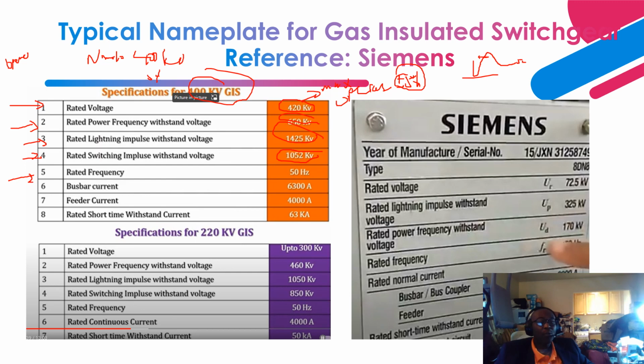Next is the rated frequency. Worldwide we either have 50 Hz or 60 Hz, right? Then the busbar current. For a GIS, we have a horizontal busbar, phase A, phase B, phase C, right? The rated current for this one is 6,300 amps. Then the feeder current is the line current that is going to the load. That's how much the feeder can withstand: 4,000 amps. That's the rating of the feeder or the line current.